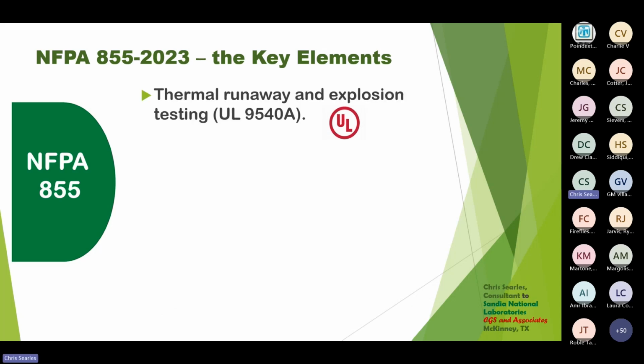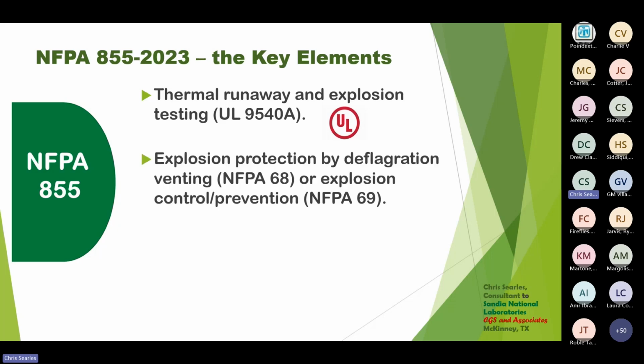Thermal runaway and explosion testing as required by 9540A is a part of the standard. Explosion protection by deflagration, which is venting of toxic gases. And there are some issues over plumes and how far they should extend and distance to boundaries. NFPA 68 deals with that. NFPA 69 deals with the actual control or prevention of it. But there's some discussion going on now that NFPA 69 may be deleted from the 2026 edition because of the issues that are technical in nature.